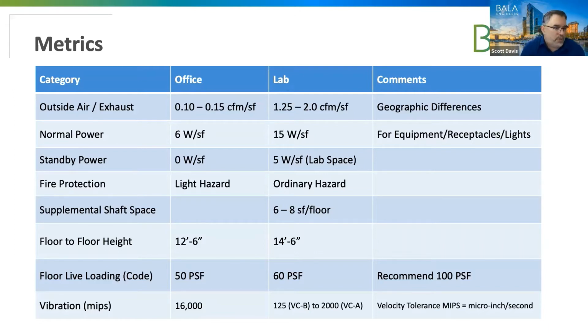So to start off, the first noticeable one is the marked increase in outside air required and exhaust. You can see your fractional CFM per square foot for an office, where we're going to be ranging between 1 and 2 CFM per square foot for a general laboratory space. The range is going to be predicated upon the type of lab space you're considering. A chemistry, heavy fume hood type lab is going to be more in the 2 CFM per square foot range, whereas a bio type lab where you have fewer fume hoods or even no fume hoods, maybe dealing mainly with biosafety cabinets that recirculate airflow, you'd be looking at 1 CFM to 1.25 CFM per square foot.